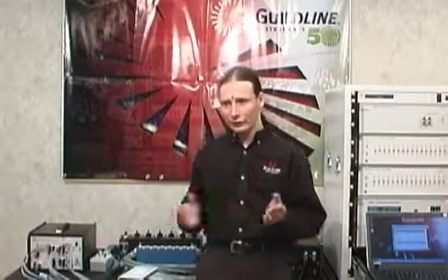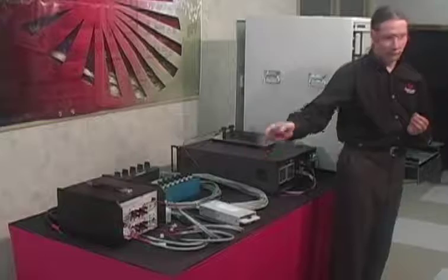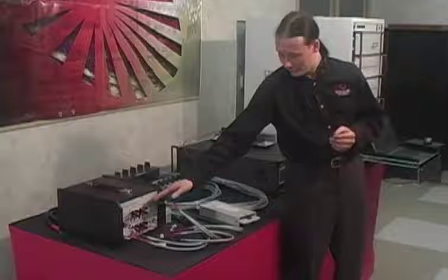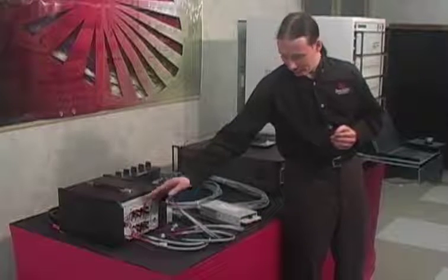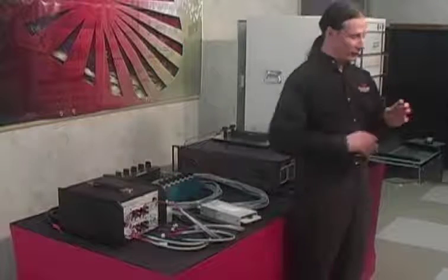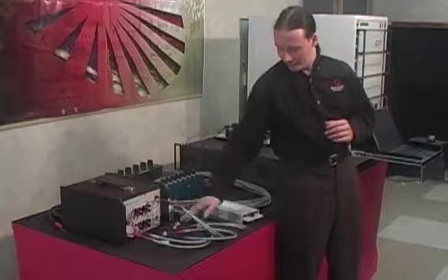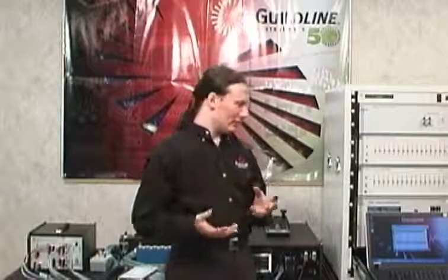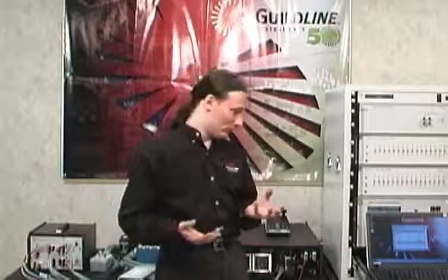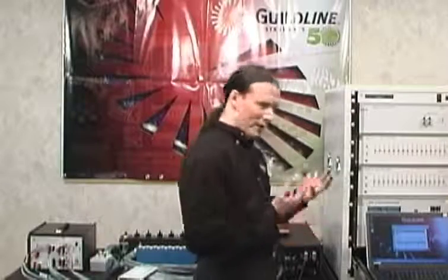So it checks those things and makes sure that as you're making these steps, the laddering makes sense with the uncertainty budgets that are prescribed for each of the resistors. So it does this from the 1 ohm to the 10K, then the 10K to the 1 meg, and then the 1 meg to the 100 meg. It checks all these ladders, and also checks the interchanges at 1 ohm, 10K, and at 1 meg, just to make sure that the ratios are making sense and the bridge is actually still measuring within what we'd expect to be its full rated accuracy as well. So it's kind of an integrity check.